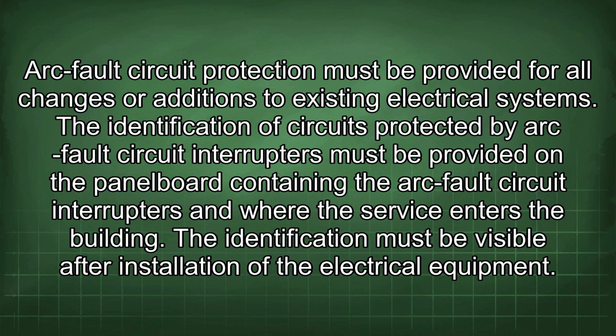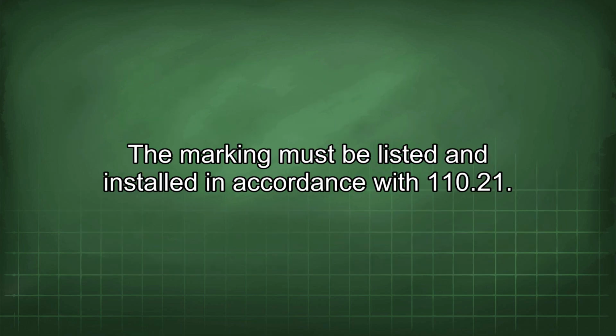The identification of circuits protected by arc fault circuit interrupters must be provided on the panel board containing the arc fault circuit interrupters and where the service enters the building. The identification must be visible after installation of the electrical equipment. The marking must be listed and installed in accordance with 110.21.